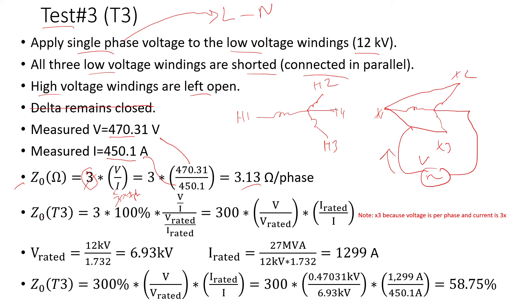The zero sequence impedance from Test 3 in percent is: 3 × 100% × (measured voltage / measured current), all divided by (rated voltage / rated current). Rearranging, that's 300 times the measured voltage divided by the rated voltage, times the rated current divided by the measured current.